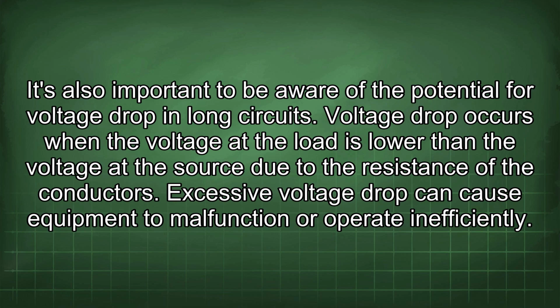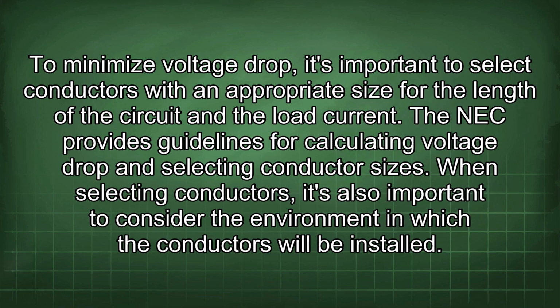Voltage drop occurs when the voltage at the load is lower than the voltage at the source due to the resistance of the conductors. Excessive voltage drop can cause equipment to malfunction or operate inefficiently. To minimize voltage drop, it's important to select conductors with an appropriate size for the length of the circuit and the load current. The NEC provides guidelines for calculating voltage drop and selecting conductor sizes.